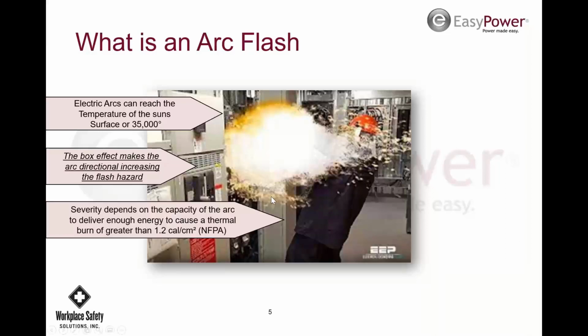So the severity depends on the arc to have enough energy to cause a thermal burn of greater than 1.2 calories per square centimeter. So for those of you that are new to this, calories per square centimeter is the measure of the incident energy level that you have. When you think of calories, you think of running or eating calories and that kind of thing. It is a measure of energy. This incident energy, as I mentioned, has the two components, a heat component and a pressure component. So 1.2 is the demarcation between a first degree burn and a second degree burn.